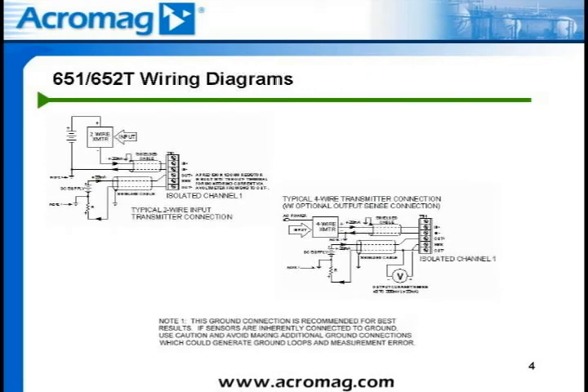Here we show electrical hookups based on DC current applications. First, we have a two-wire transmitter field device, which involves the use of a DC power supply to power both the field transmitter and the input loop. Going around the loop starting with the positive terminal of the two-wire transmitter, wired to the positive side of the DC power supply. From the negative side of the power supply, wired to the IN- terminal of the 651T or 652T transmitter. The negative connection on the two-wire transmitter ties in with the IN+ terminal on the 651T or 652T module.